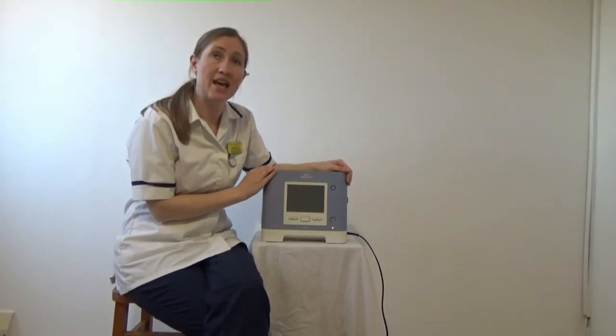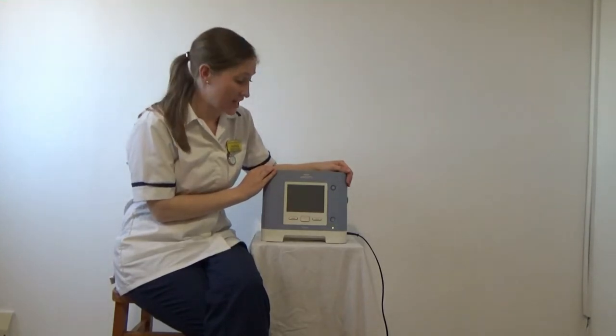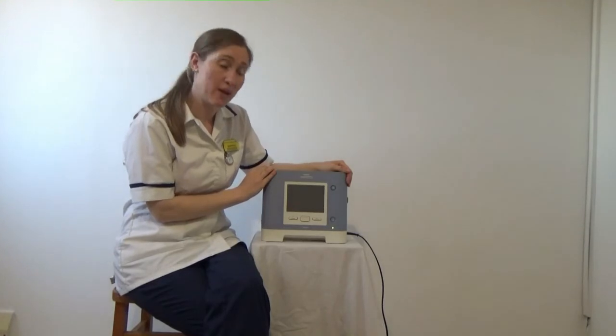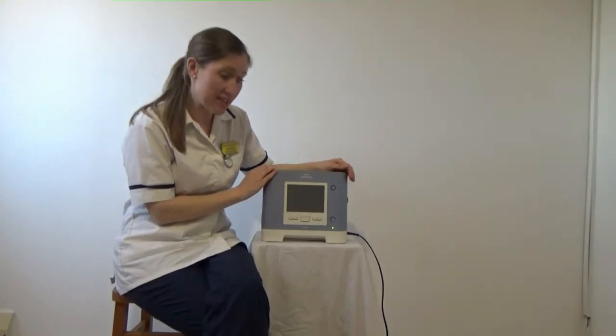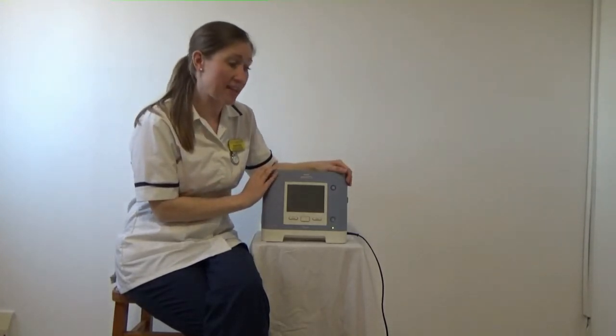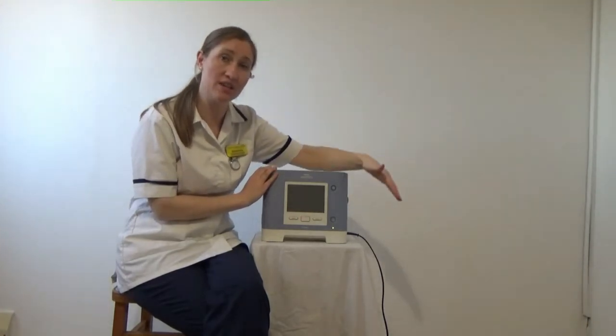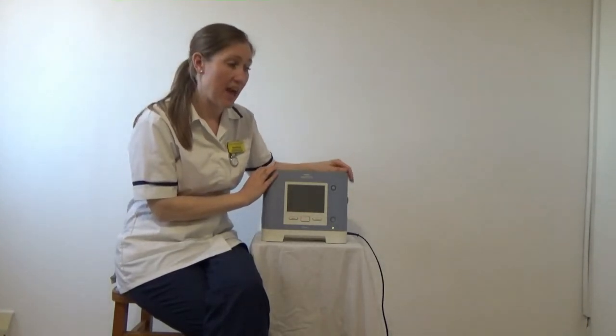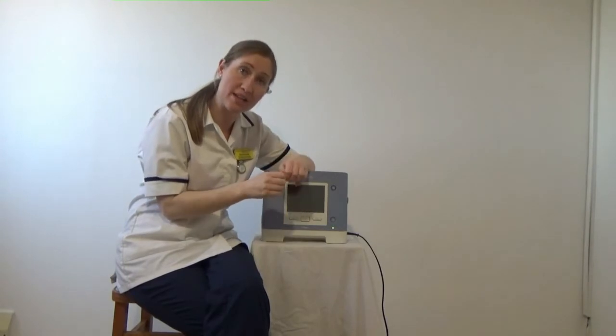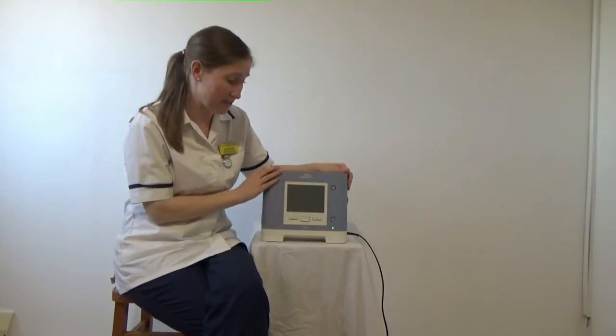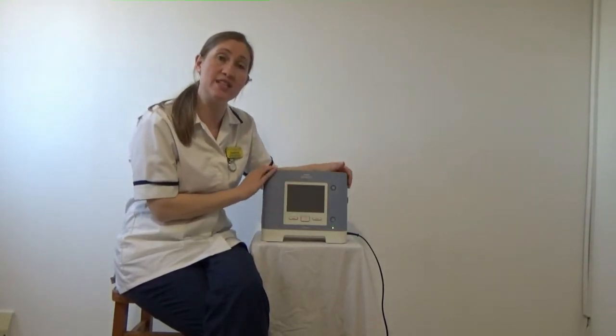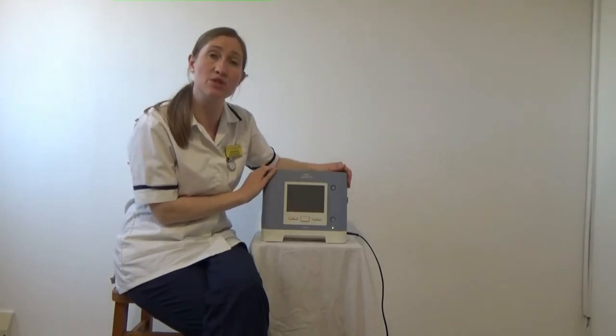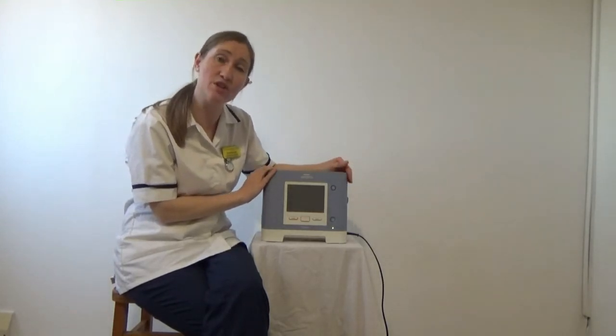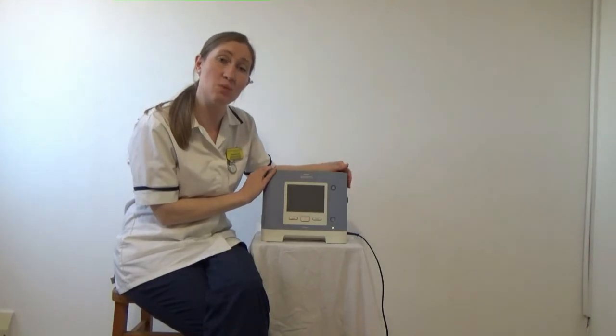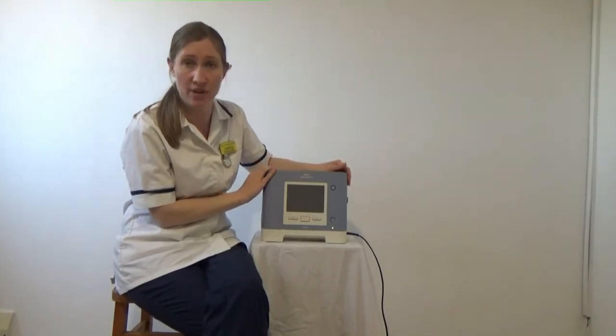Alarms that indicate there is a leak in the circuit include circuit disconnection and low inspiratory pressure. These suggest that there is a leak somewhere. Again, check that each connection is connected thoroughly and also that the hose has not split, which can also cause a leak. Again, if you have checked all of these and this alarm still sounds, you may want to either change the circuit for a new one, and if that still doesn't work, contact your NIV department for further advice.